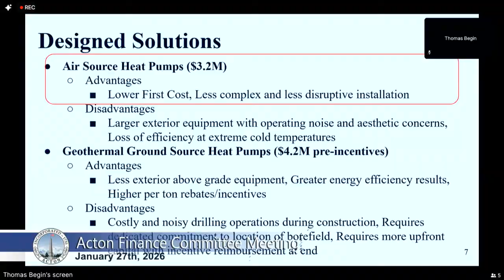Does there need to be another backup heat source contemplated? The air source system we've designed includes redundancy—it's an all air source heat pump system designed for N+1 redundancy. If you lose a module, you've got backup modules, so if one needs repair, the others keep the building fully heated.